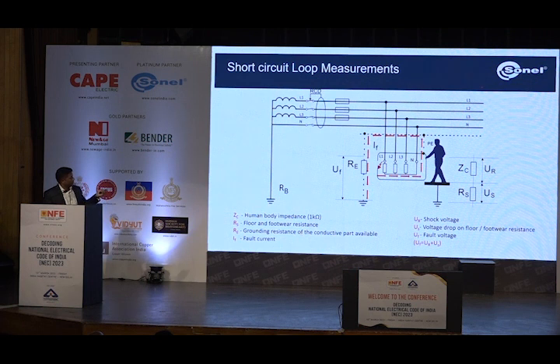So in this total path of loop impedance measurement, what we try to do here is not very complicated - it's Ohm's law. You connect an equipment, calculate the prospective short circuit current, and you are able to estimate the impedance of the circuit. It's not a complicated scenario.